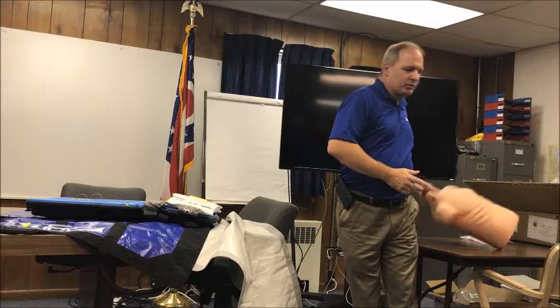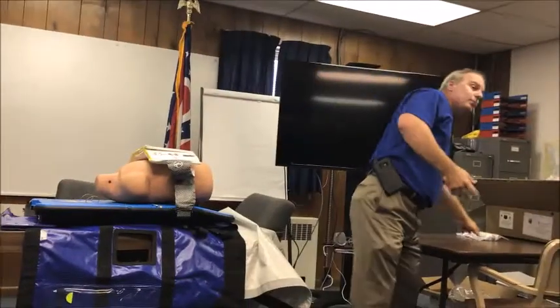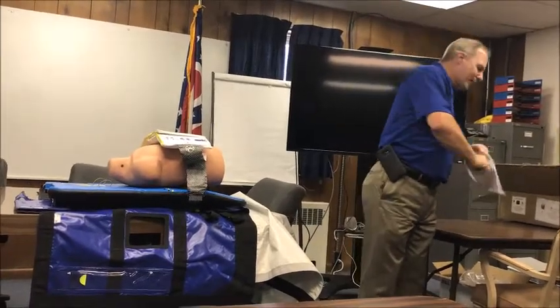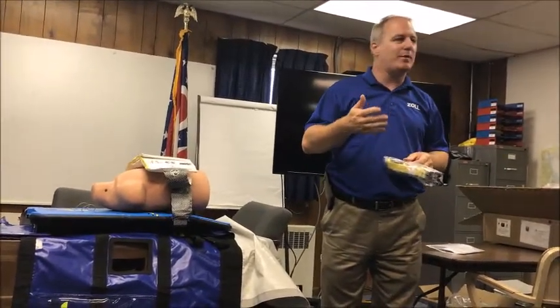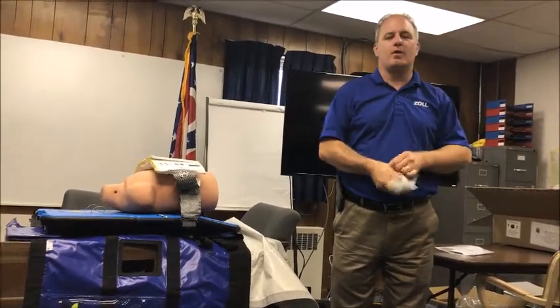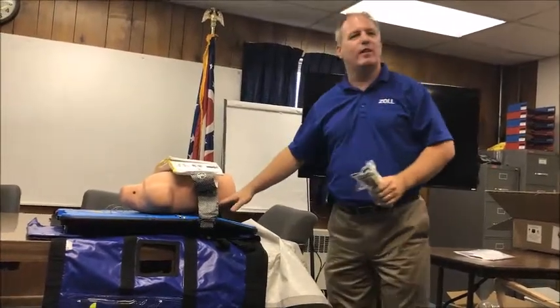Once you get the patient on the AutoPulse, at some point in time you're probably going to want to transport. The best advice I can give you is remember when I told you that if the AutoPulse stops, it's trying to tell you something. The most common cause of the AutoPulse stopping is that the patient's back somehow gets lifted off the board.